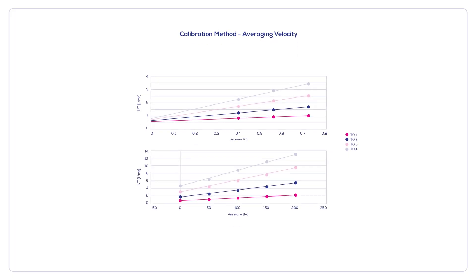TRPS is a calibration-based method that measures the differential electrokinetic mobility of the agents while passing through a nanopore with respect to different applied voltages. Zeta potentials are then calculated from the measured mobilities based on this approximation. As a calibration technique, TRPS zeta potential measurements require precise knowledge of the zeta potentials of a standard particle and the nanopore or membrane material. The method also considers particle transport due to convection, which is determined by evaluating particle speed versus applied pressure. TRPS can perform simultaneous size and zeta potential particle-by-particle measurements.